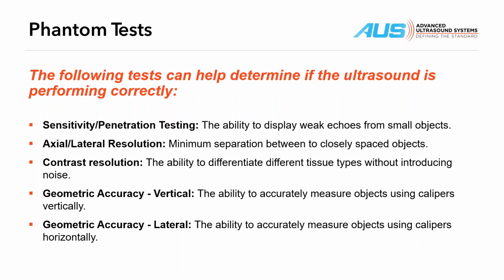Axial, lateral resolution, we defined them. Again, what we're looking for is the minimum separation between two closely spaced objects. On the 539, the phantom that we use and I recommend, it's not because there aren't any good phantoms or other phantoms aren't good. I'm not suggesting that they're not good. They all image very well. There's some very good ones out there. The reason I like the ATS or the CIRS now, who bought out ATS Phantom, is because there's no PM required on them. There's no liquid inside them, no fluid that evaporates over time.